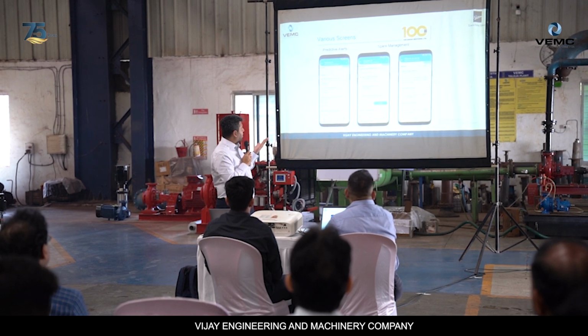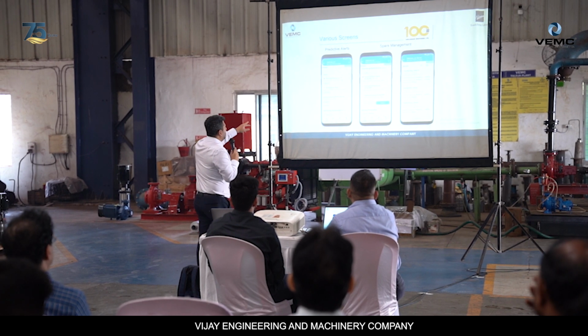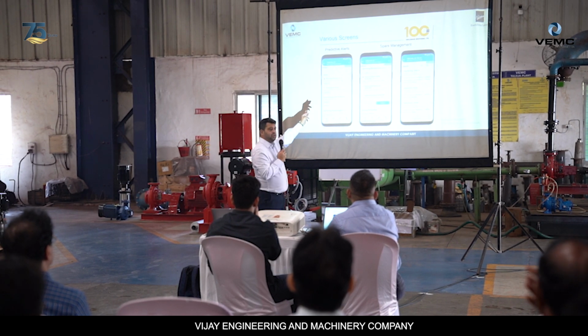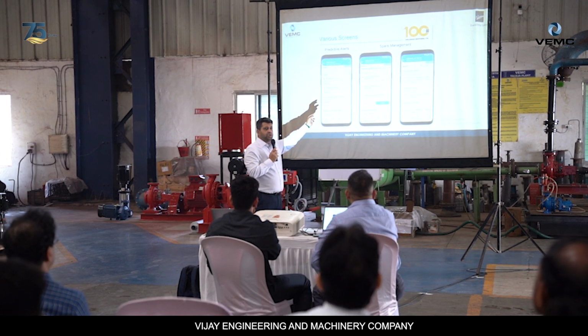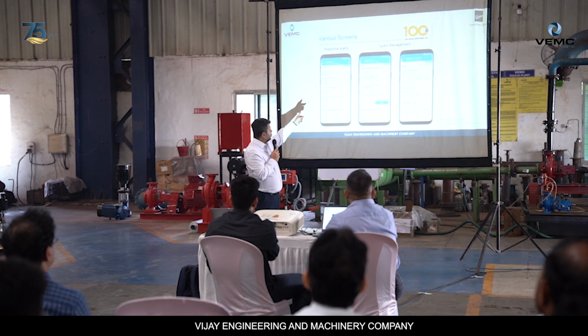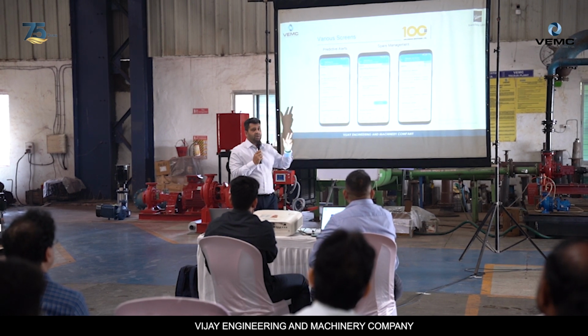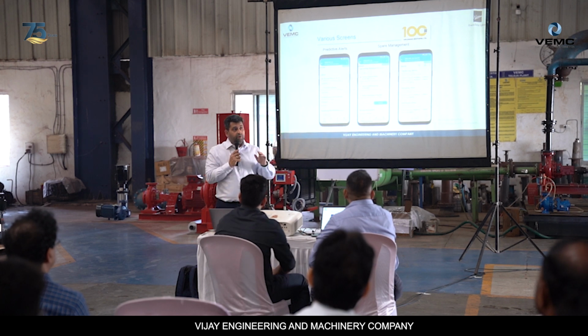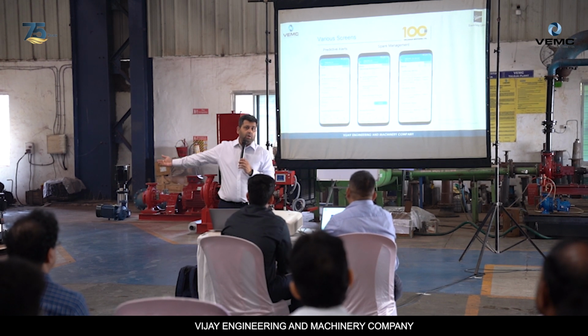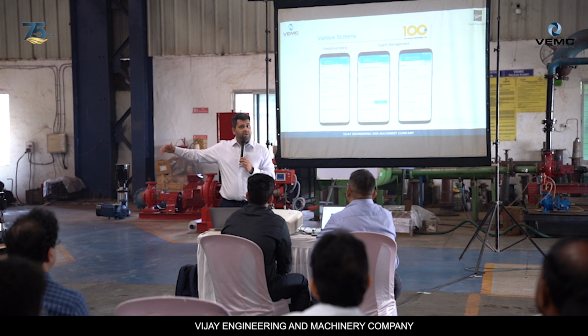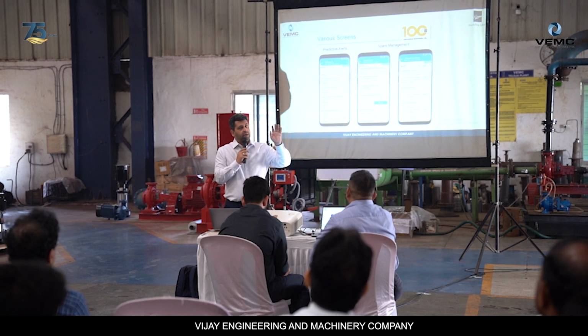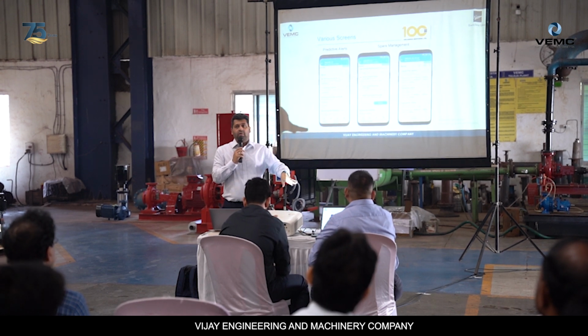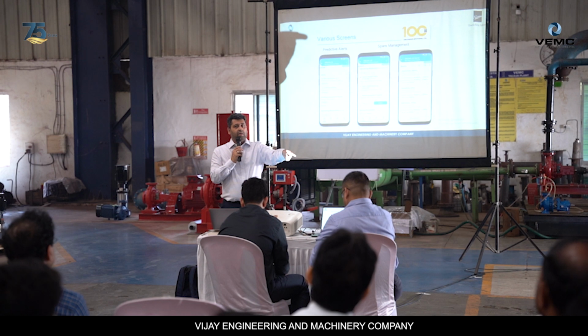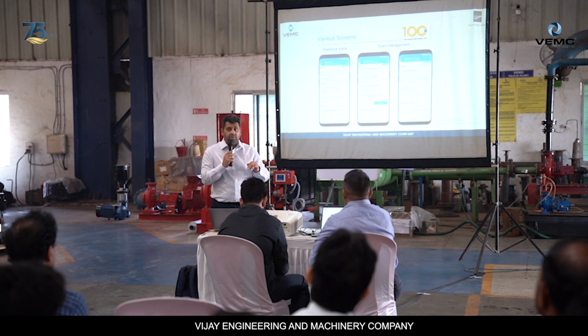Predictive maintenance and spare management. If you look, it says cavitation condition, that's the predefined cavitation conditions in terms of behavior. So it would give you an alert if there is some kind of cavitation condition happening, so please take note of it. What happens is we come to the outer end of things - once the cavitation has happened, the pitting marks are there on the impeller, the problem is already there. Now that doesn't make a solution. Suppose if there is a problem, at least there is an opportunity for me to address it.